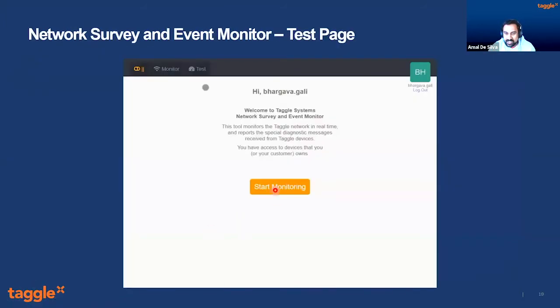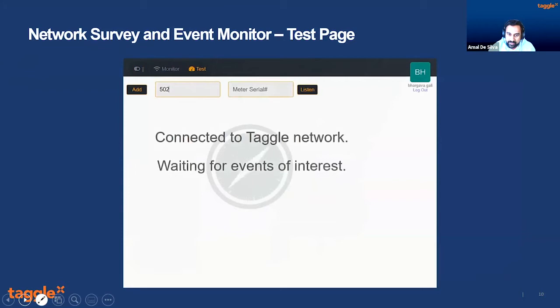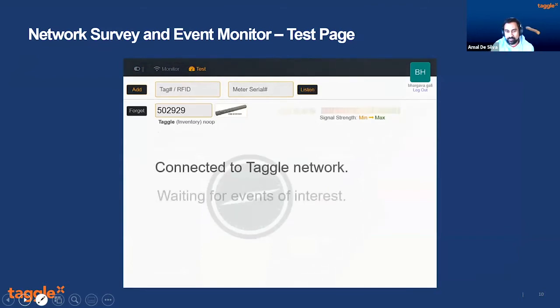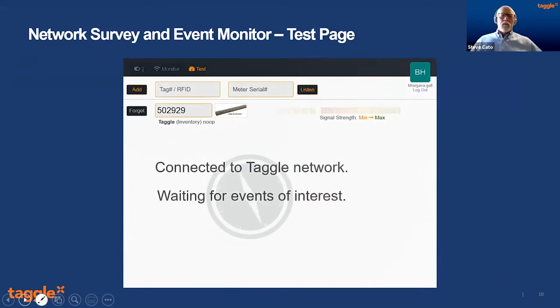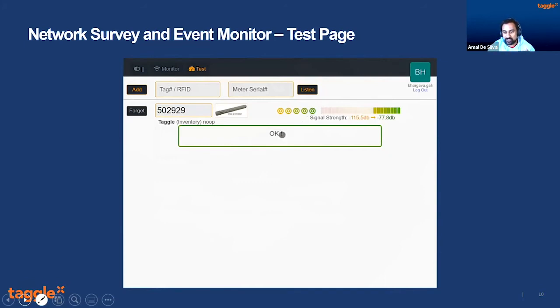There are two parts of the survey page. In the test tab: Bhargava is going to click on test, with tag ID 502929. He'll put that in and hit listen, then hold the device where he's going to install it and swipe with a magnet. You should see five transmissions come through — shown as five dots. The green box at the bottom tells you it's commissionable. If it's coming in at a weak signal strength, it'll tell you to try raising it higher or use a higher power device. Signal strengths are shown on the bar on the right. Anything up until negative 130 dBm is commissionable.